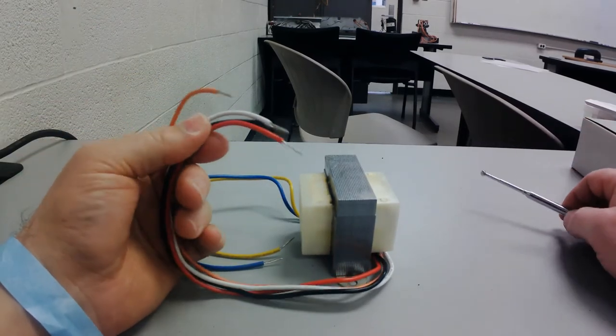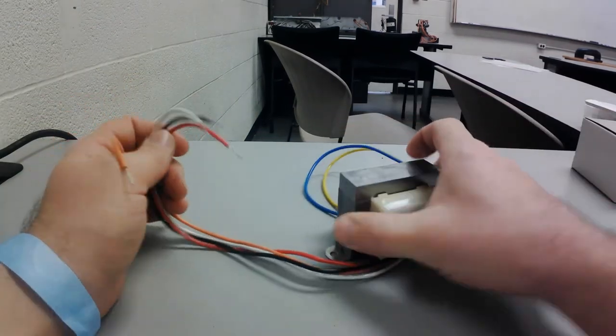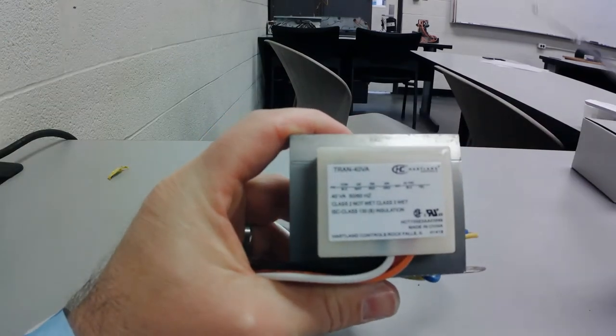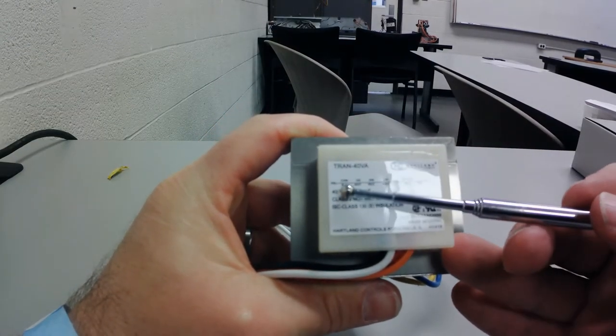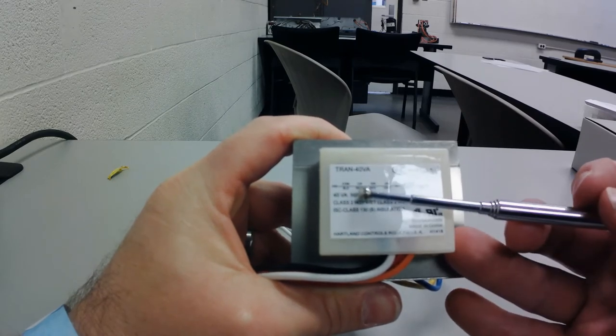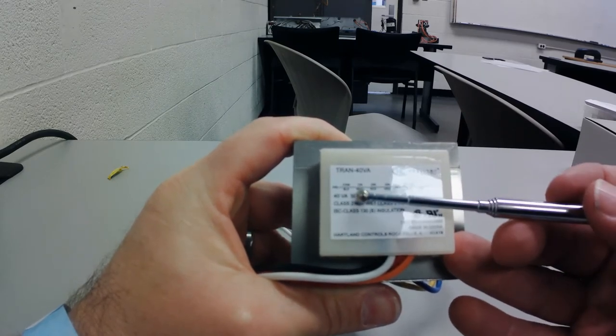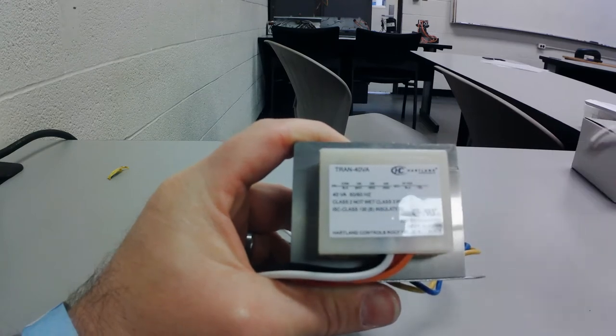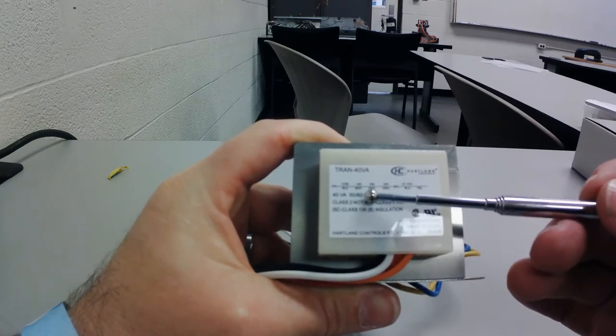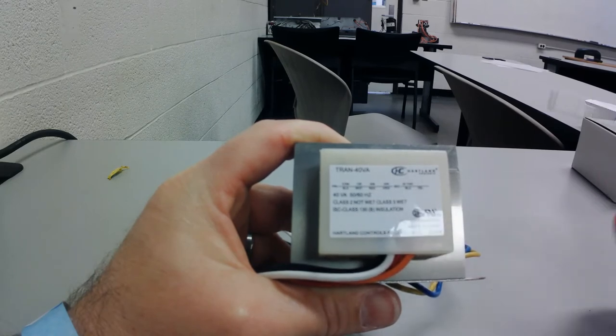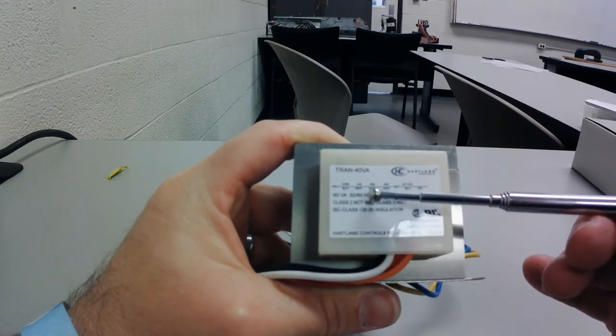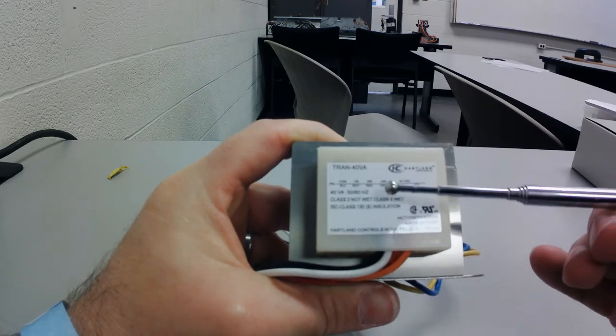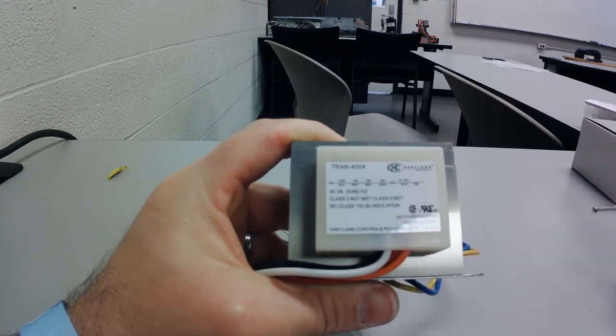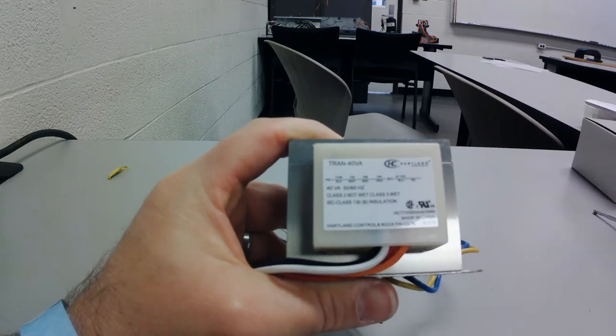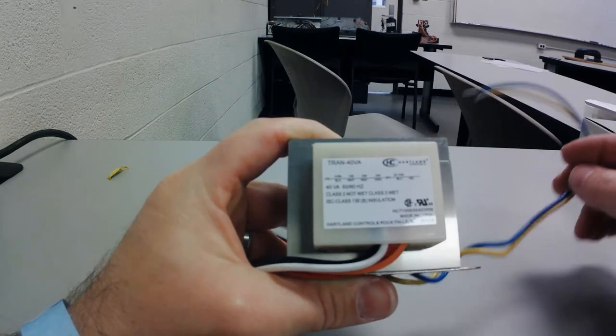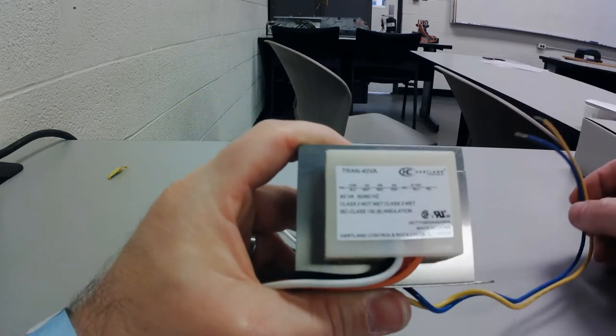We're going to look at these other wires. I am sitting next to a 120 volt power source. So if I were to look at the data plate on this one, common in this case is always black. And if I'm going to hook it to a 120 volt power source, I'm going to use the white. And that's a common theme throughout the field, but always read the data plate to make sure. Red is going to be 208. So if I had 208 in an air handler, a package unit, what have you, I would use the red and the black. And then 240 is going to be your orange and black, as we see here. No matter what, blue and yellow is always the 24 volt side. They are always by themselves over here. No extra wires on the secondary side.